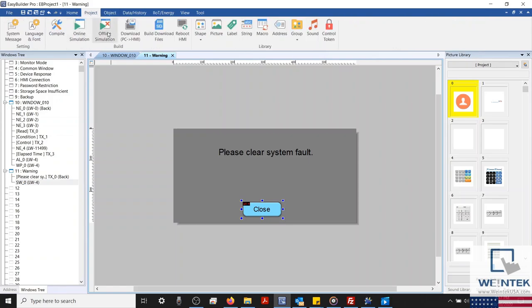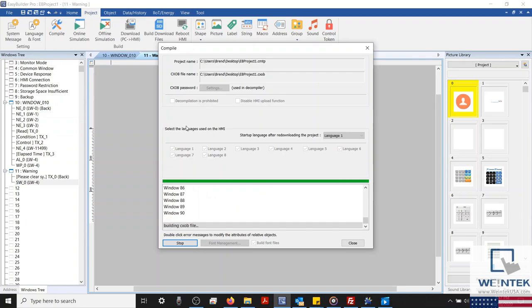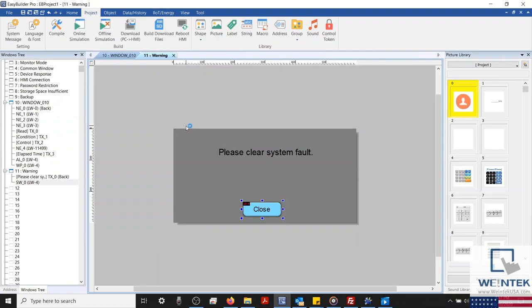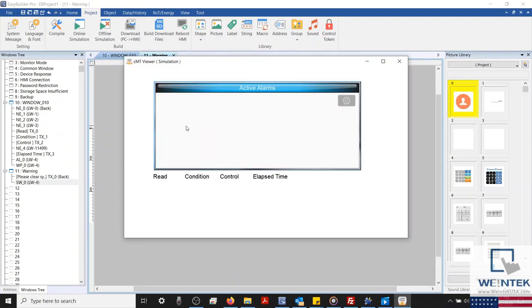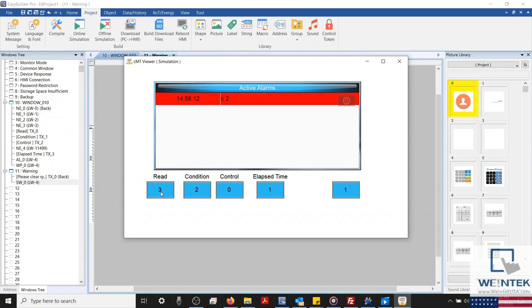With our simulation running, let's configure our dynamic condition value. I'll set this to 2. And next, let's trigger our alarm. Because our alarm's condition states that it must be larger than the condition value, we'll set our read address to 3. And you'll see that our alarm's message shows C2. I'll change our read address to 4. And the message changes to D2. This occurs because our string table determines what label is shown based on the value entered within our read address. It also uses the multi-watch syntax to display the number entered within our alarm's condition value. This is kind of an odd configuration, but is only for demonstration purposes.